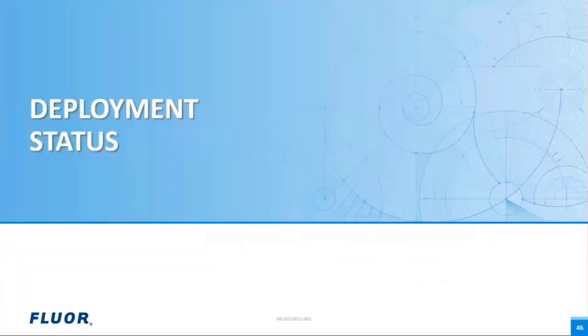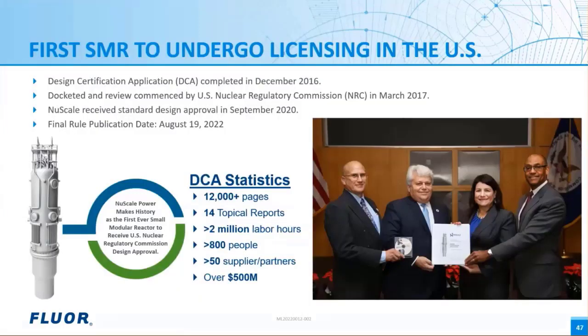So what's the deployment status of this reactor? The design certification, as we said, is completed for the 50 megawatt version and underway for the 77 megawatts. And as I mentioned, NuScale is about 4 years ahead of our competitors in this. Those competitors have not yet submitted their designs for review to the Nuclear Regulatory Commission. The NuScale application was quite extensive, with over 12,000 pages submitted, including 14 topical reports. It required greater than 2 million labor hours and cost over $500 million to get that standard design done and approved by the NRC for the 50 megawatt plant.